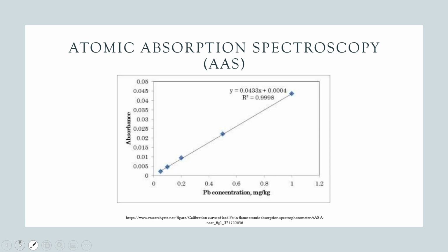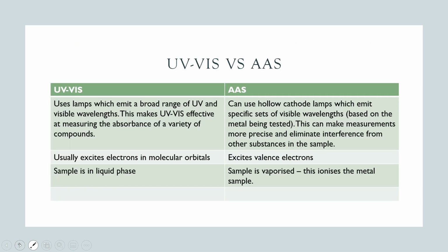Then we're able to construct a calibration curve very similarly to the way that we did before and use that to find the concentration of contaminants in a sample. So they are really similar. There are some differences though with UV Vis and AAS, and it's mostly got to do with the lamps that are used. UV Vis has a lamp that's able to emit a very broad range of visible and UV wavelengths, making it good for measuring a whole range of different kinds of compounds.